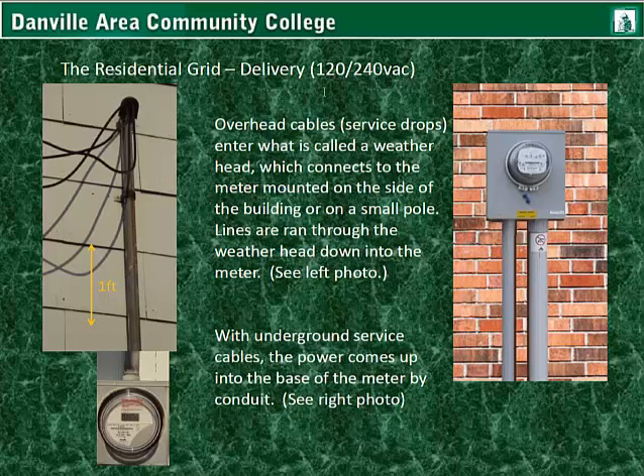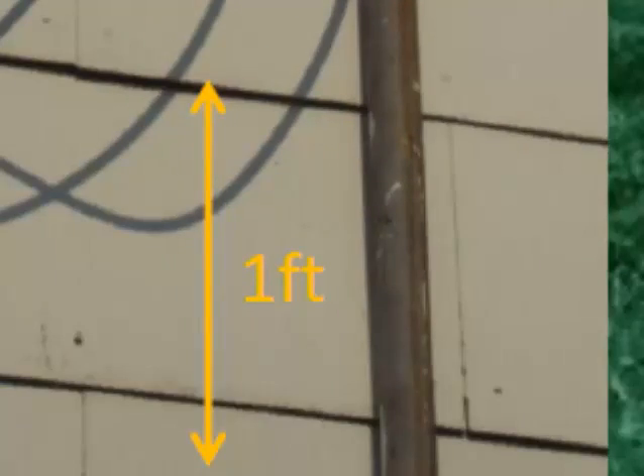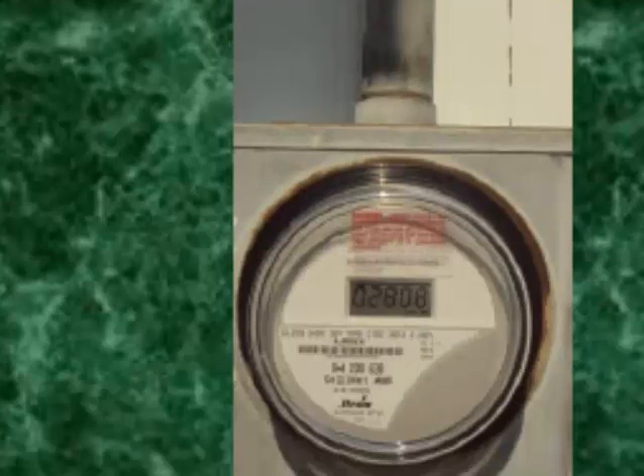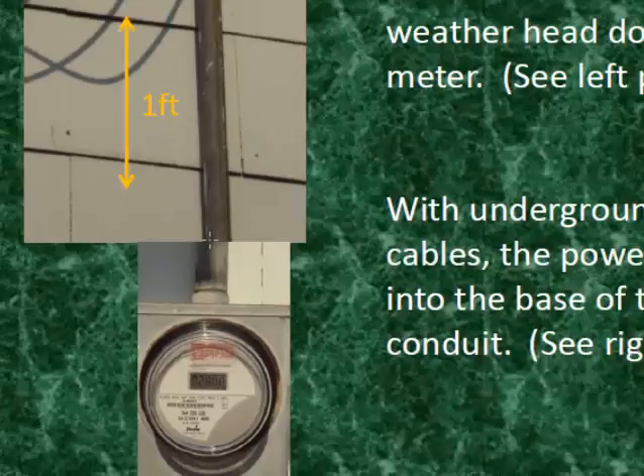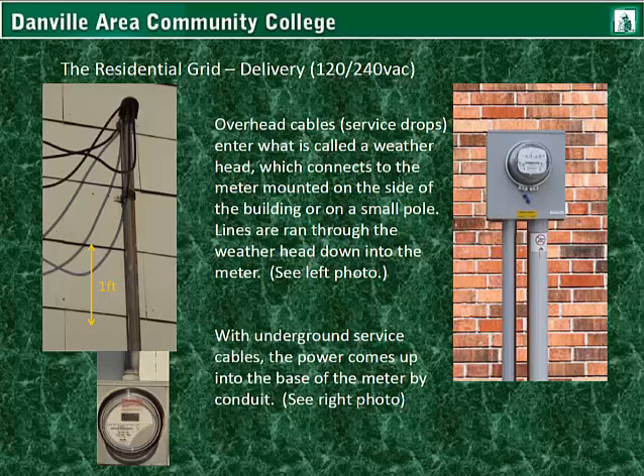Here in the U.S. we deliver 120 and 240 volts AC. The transformer is a center tap type, so two of the lines are connected to the entire secondary of the transformer, so it gets all of the voltage. Overhead cables, or service drops, enter what is called a weather head. It connects to the meter mounted on the side of a building, and oftentimes it's mounted to a small pole near the home. With underground service cables, the power comes up into the base of the meter by conduit.